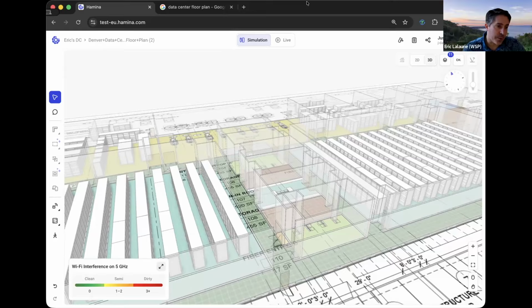What can impact your propagation here that's not shown on this are the hot aisle containment systems. It varies depending on the size of the data center, but typically a large data center, hyperscale, or someone like Microsoft or Google will have a hot aisle containment system, what we call a HACS. Essentially, every 2 rows you'll have that system - usually it's like polycarbonate with some structural support, and it encloses the hot side of the servers.